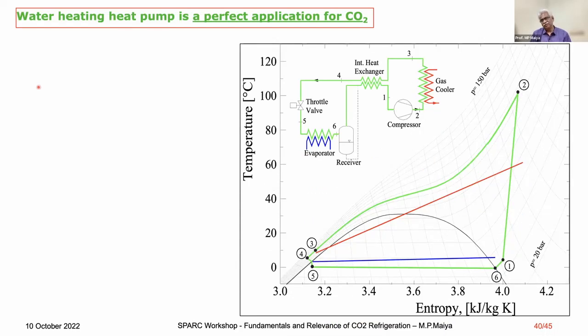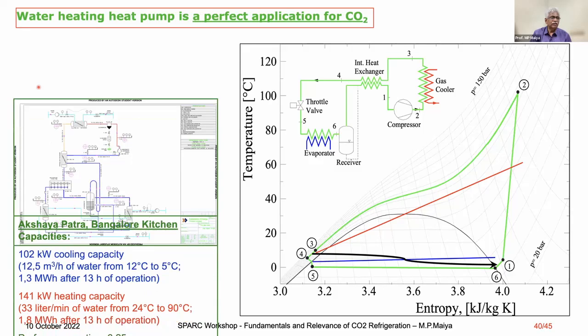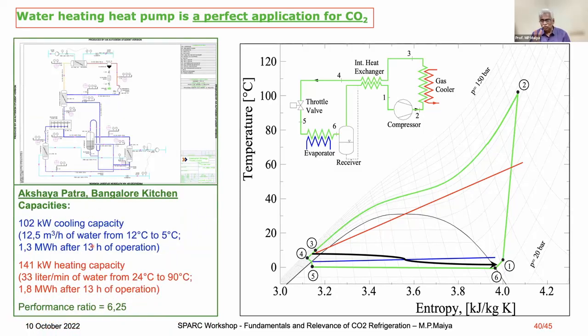Again, a water heating pump is a perfect application. You can see we are using it for a centralized kitchen. Here, we get 1/3 diesel saving for heating. For cooking, you need to preheat the water, then boil. So we take care of the preheating of the water from 25 degrees centigrade to 90 degrees centigrade. That accounts for 1/3 of the fuel, so a great saving. Overall COP becomes 6.25, including heating. And even here we need this IHX, which will boost this temperature. Without IHX, temperature will be less. It's not sufficient. We have to boost it. Of course, we need IHX to safeguard the compressor, to boost the discharge temperature, and if possible, increase the COP and so on.